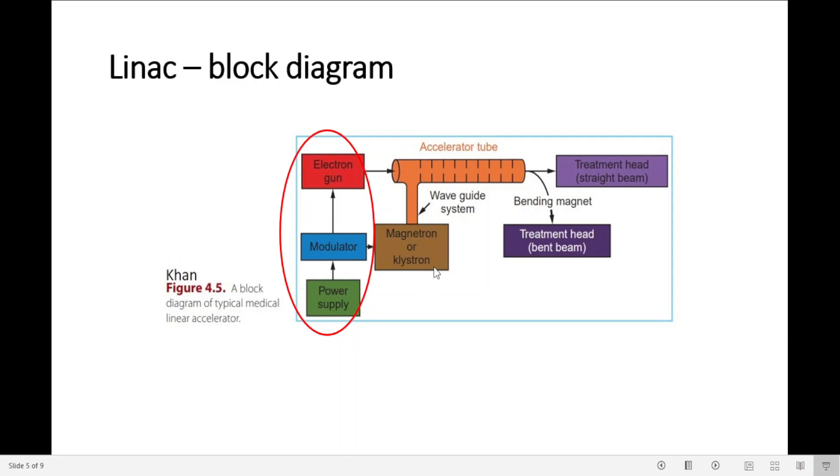And a klystron is a microwave amplifier. It's not a generator. It's only an amplifier. If the LINAC has klystron, it also needs a low power microwave generator, the RF driver. The pulsed microwaves generated in this system are injected into the accelerator tube through the waveguide system, which is this part here.